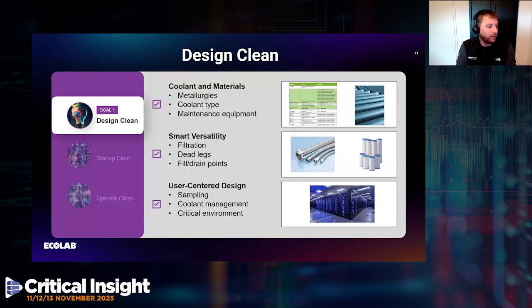So to start with design clean, what we often want you to consider are the metallurgies used — especially copper and aluminum are some that need careful and tight consideration. Also the coolant type you use, whether it's a glycol-based mixture or more water-based, any maintenance equipment you might have, and related to that, what kind of filtration is already designed into the loop.